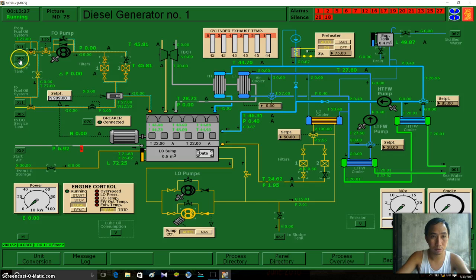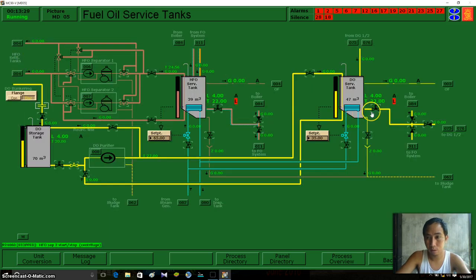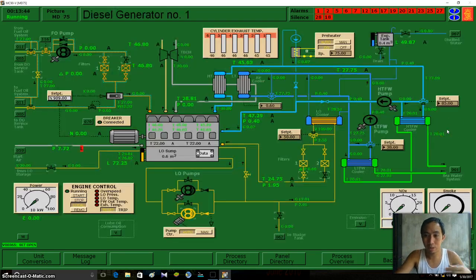Okay, so we're going to check our diesel oil service tank. So from our service tank, we have our shut-off valve here. This is a quick closing valve in case of emergency. We're going to switch it on and switch on the line going to our diesel generator 1 and number 2. Go back to diesel generator number 1. So now the only problem that we have is our starting air system.